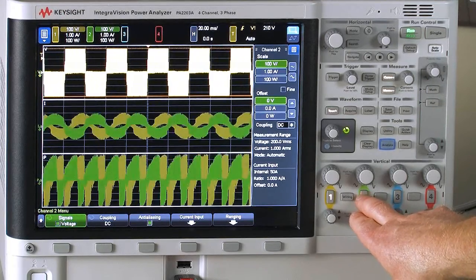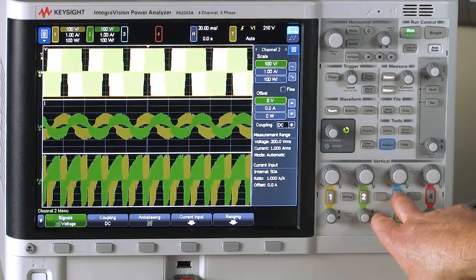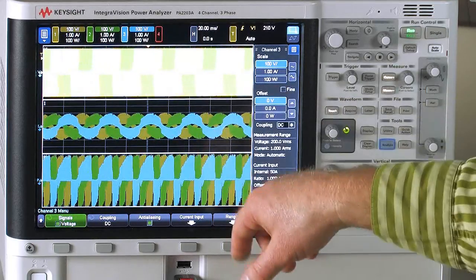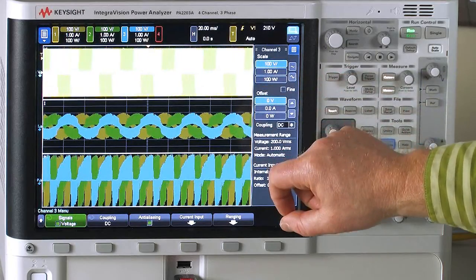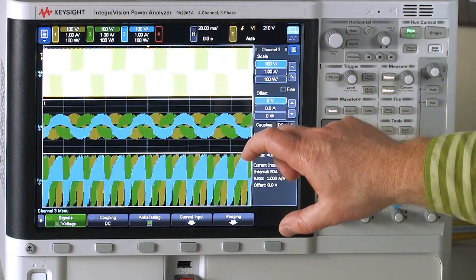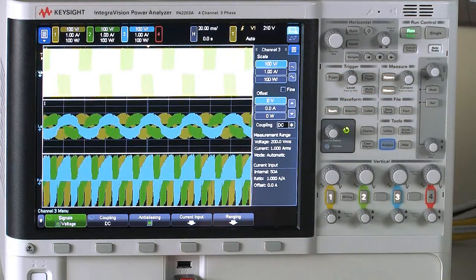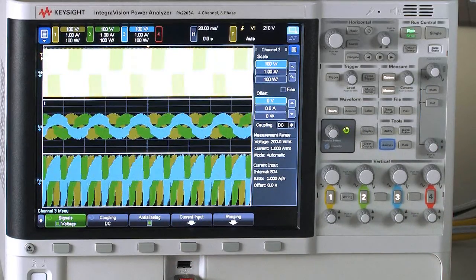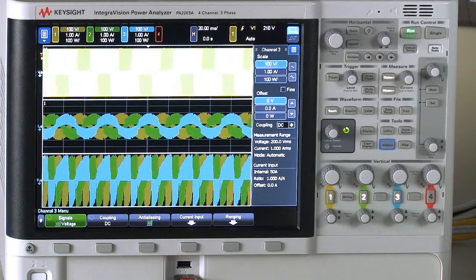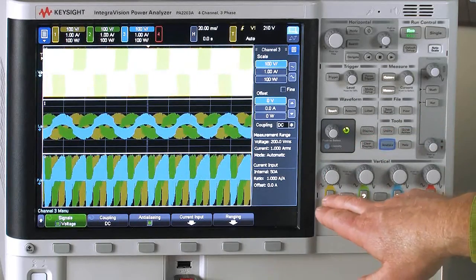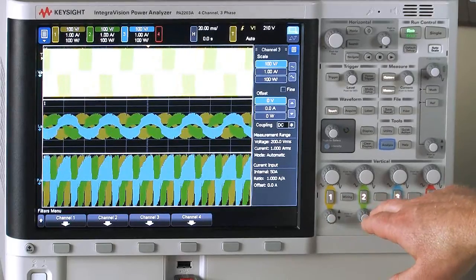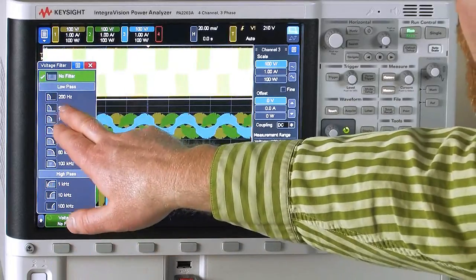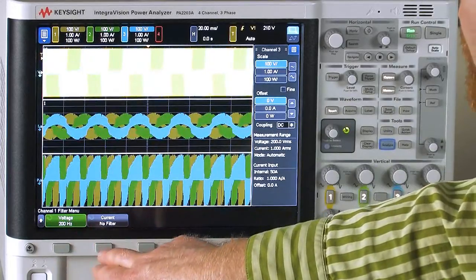And then I can zoom out and look at all of the channels here. So channel two is phase two or V, and channel three is phase three or W. So I'm measuring directly across each one of those delta configuration legs, and I'm measuring the current going into it. You can see the current's somewhat sinusoidal.